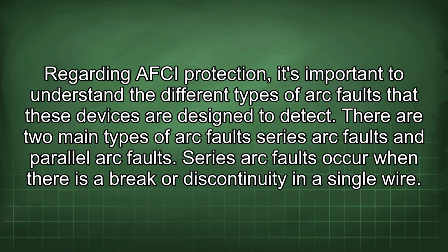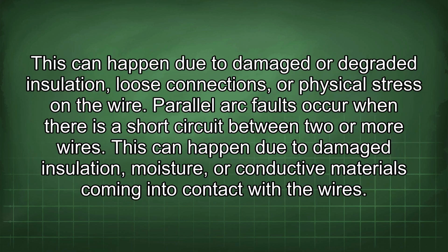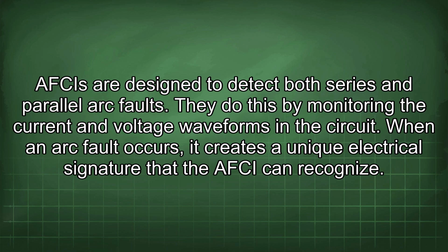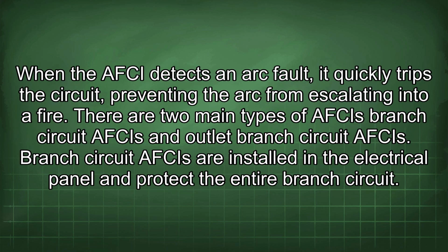Series arc faults occur when there is a break or discontinuity in a single wire. This can happen due to damaged or degraded insulation, loose connections, or physical stress on the wire. Parallel arc faults occur when there is a short circuit between two or more wires. This can happen due to damaged insulation, moisture, or conductive materials coming into contact with the wires. AFCIs are designed to detect both series and parallel arc faults. They do this by monitoring the current and voltage waveforms in the circuit. When an arc fault occurs, it creates a unique electrical signature that the AFCI can recognize. When the AFCI detects an arc fault, it quickly trips the circuit, preventing the arc from escalating into a fire.